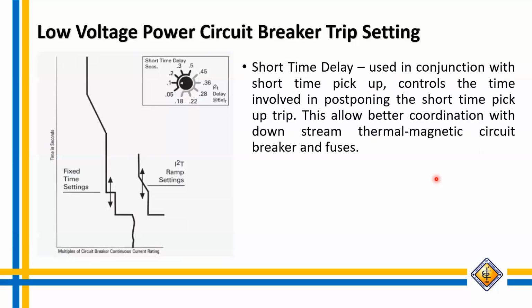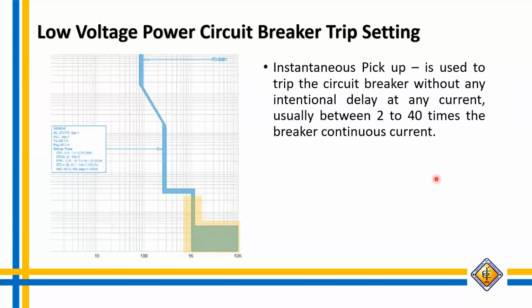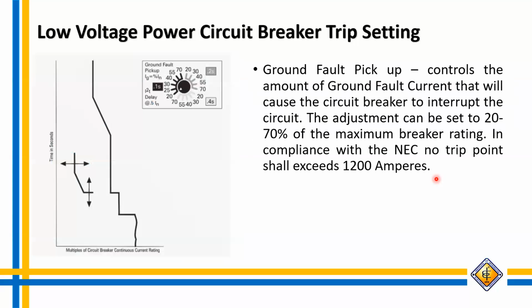So the short time delay, used in conjunction with the short time pickup, controls the time involved in postponing the short time pickup trip. This allows better coordination with the downstream thermal magnetic circuit breaker and fuses. Instantaneous, as we all know, is used to trip the circuit breaker without any intentional delay at any current, usually between 2 to 40 times the breaker continuous operating current. Ground fault pickup controls the amount of ground fault current that will cause the circuit breaker to interrupt the circuit. The adjustment can be set to 20 to 70% of the maximum breaker rating. In compliance with NEC, no trip point shall exceed 1,200 amperes.